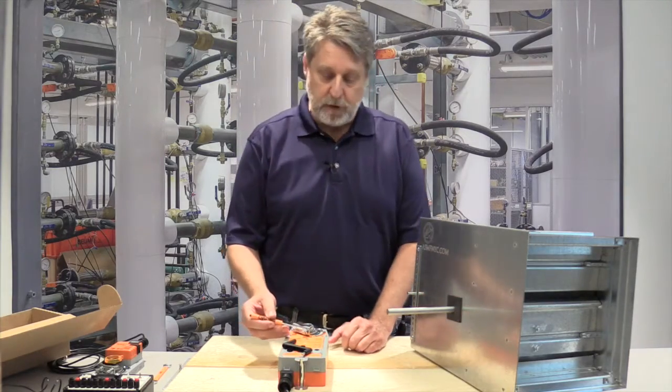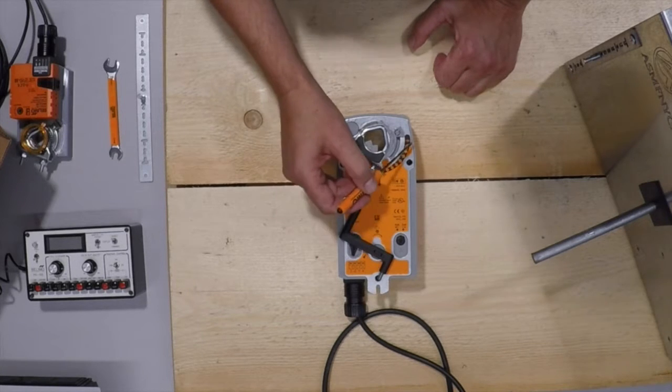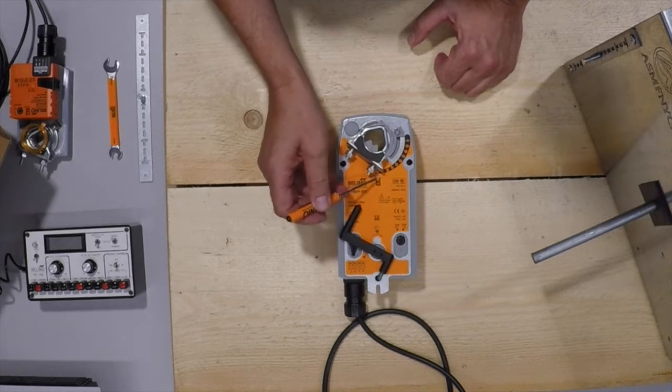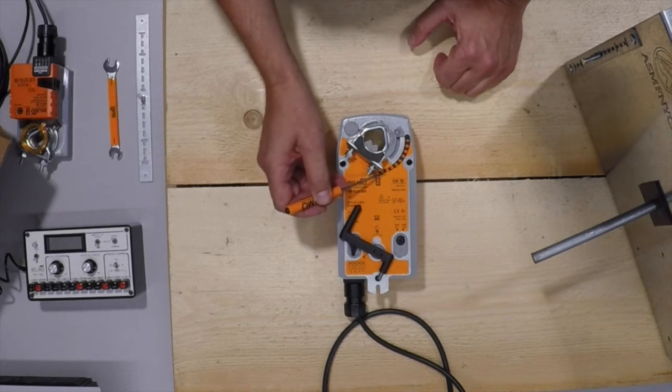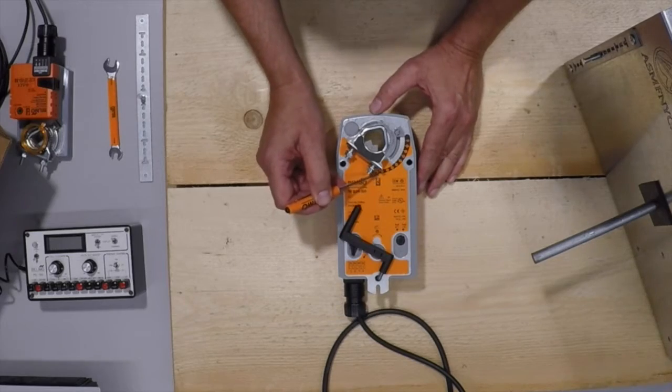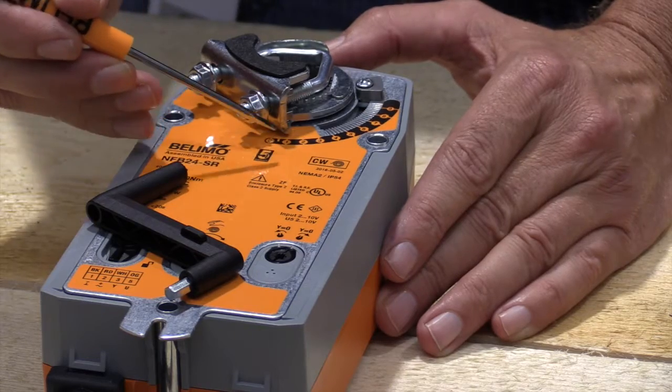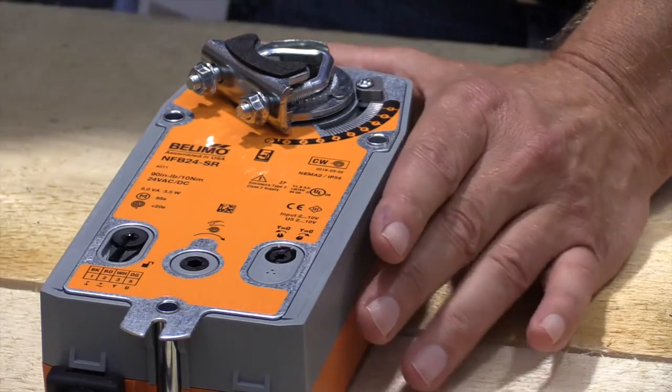If you look on the face of the actuator, there's a black scale with numbers from zero to ninety. Each separation is 10 degrees. If you notice, there's a little tick mark between the zero and the one, and that's five degrees. It comes from the factory preset.